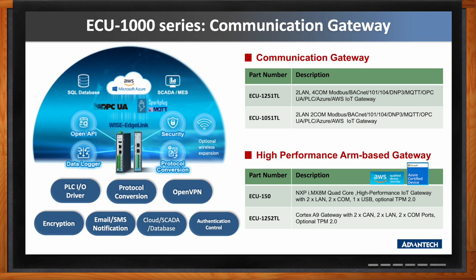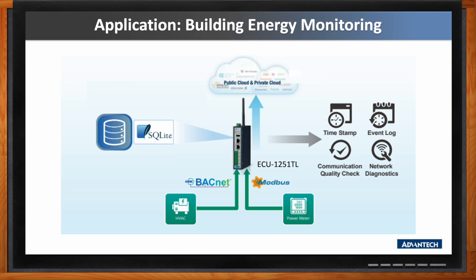The ECU-1252 also comes with two CAN ports. Now let's talk about applications. What kind of applications are these gateways a good fit for? One application is building energy monitoring. To manage equipment like HVAC and power meters and collect data, the ECU-1251 is used to communicate with the HVAC and meters via different protocols like BACnet and Modbus. After collecting data from the equipment and meters, the gateway sends the information to the cloud and database. The data also comes with timestamps for further data analysis, and a watchdog checks the system regularly to assure data reliability.